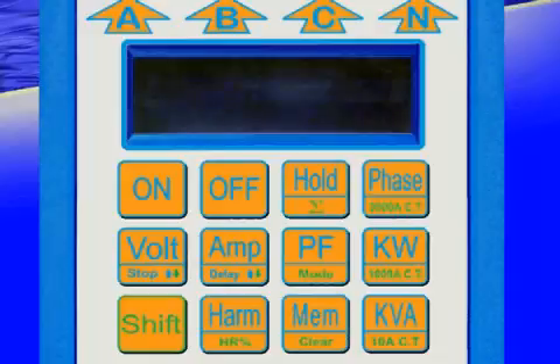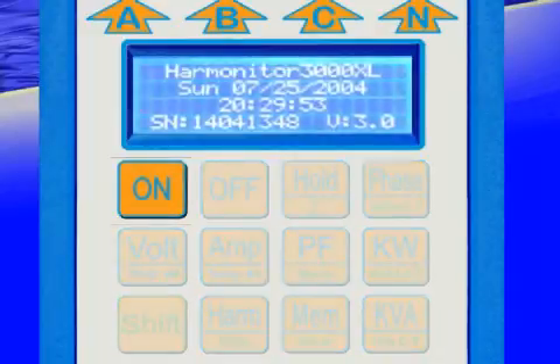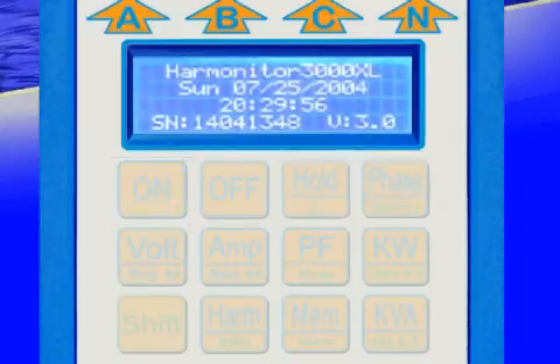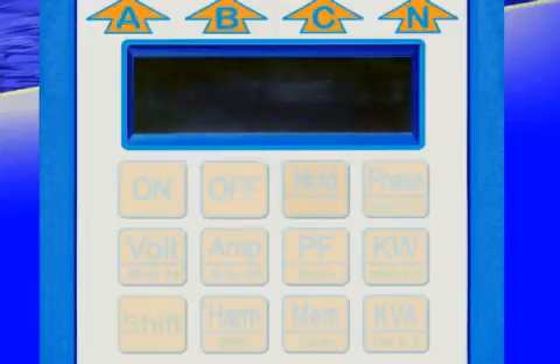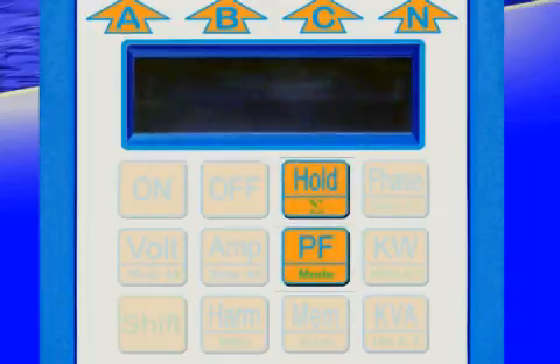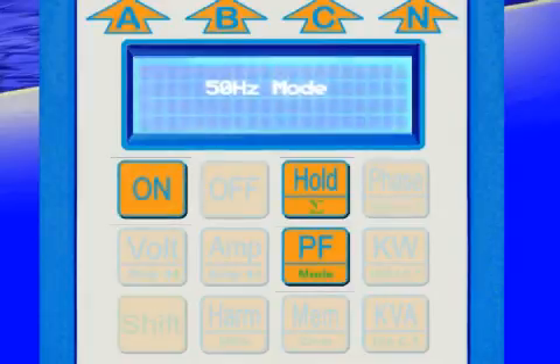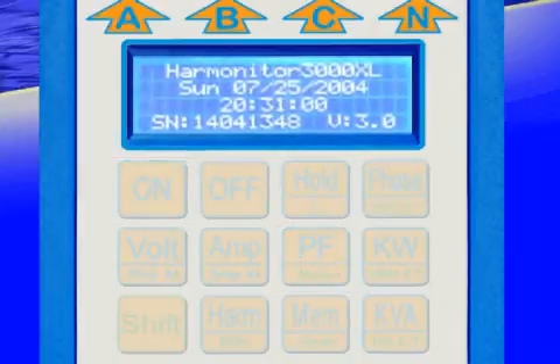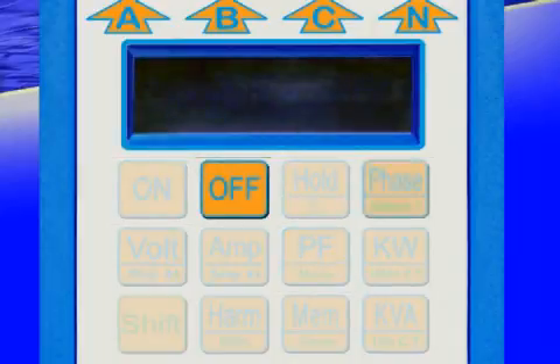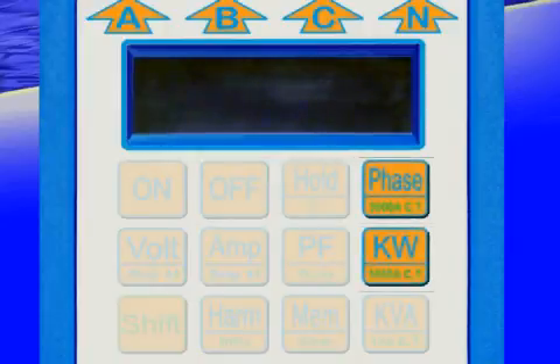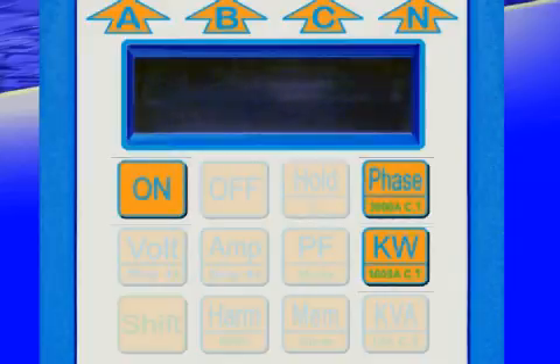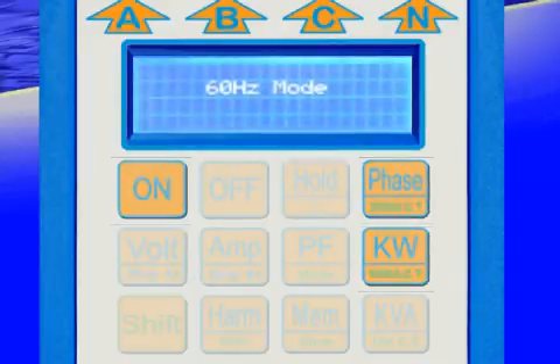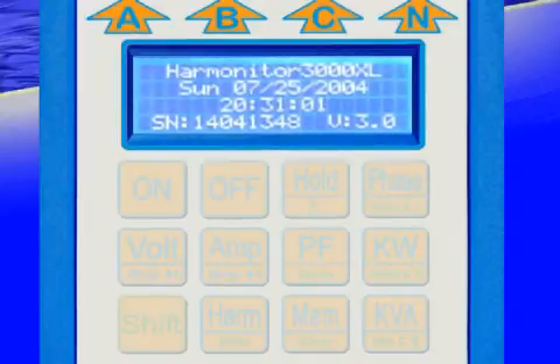After properly connecting the CTs and voltage leads, press the on button to power the unit up. If this is the first time your Harmonitor is being used in your country, you must set which frequency you will be measuring. If you're using 50 Hz, starting with the unit off, hold down the hold button, power factor button, and then press and hold the on button until you see 50 Hz mode displayed. If you're using 60 Hz, starting with the unit off, simultaneously hold down phase and kW, and then press and hold the on button until you see the 60 Hz message displayed. After setting the unit for either 50 or 60 Hz, you do not need to set it again unless you need to measure a different frequency.